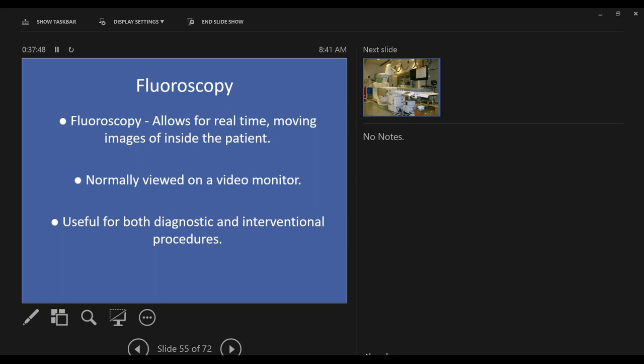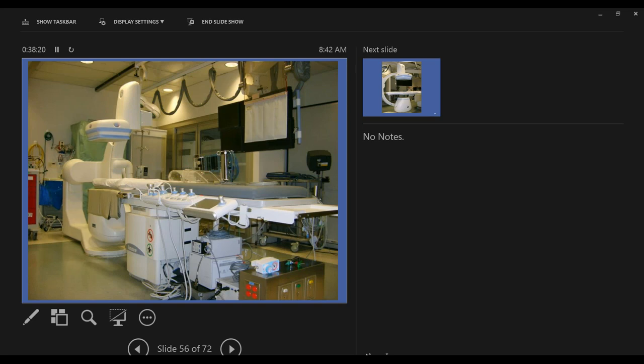Sometimes a patient goes to the cath lab after failing their stress test. Depending on the procedure level, they might just take pictures and move on, or they might fix the blockage right then and there. In a typical cath lab setup, the digital detector is on top and the x-ray tube is on the bottom, tucked behind a curtain. The x-ray beam comes up through the bottom, through the table and the patient, and up to the digital detector. The digital detector is kind of like a giant Etch A Sketch — it has a scintillator layer and a big photodiode array. The radiation goes through the front of the detector, gets converted into light, and the photodiodes record the position of each piece of light to make the image.